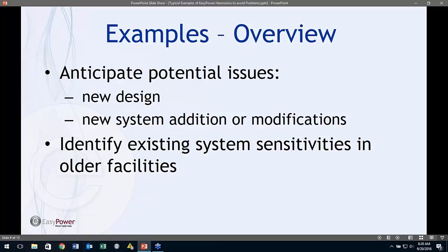What I'm going to do here is a real quick overview, a snapshot of a system, and isolate or potentially focus on areas that could have problems or potentially be problems just based upon the data we collected during our flash study. So it's a starting point. It's a point to have a conversation with the client because he knows, or they know, where they have harmonic sources, and therein lies the challenge of trying to close this loop.